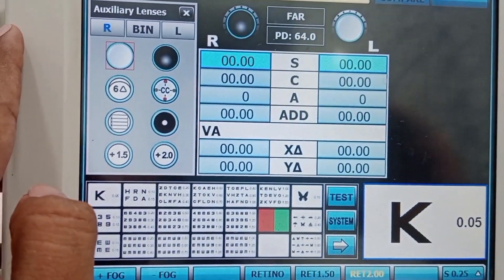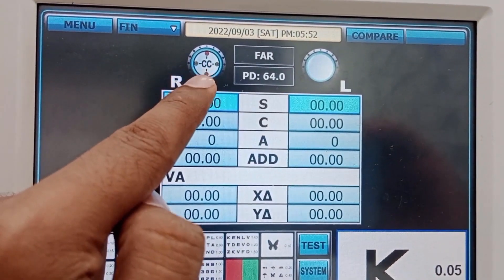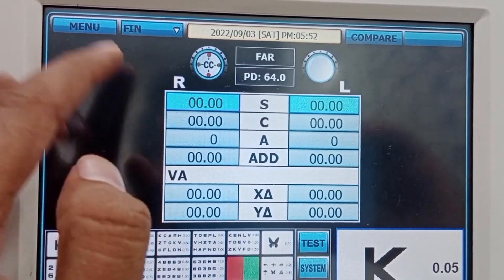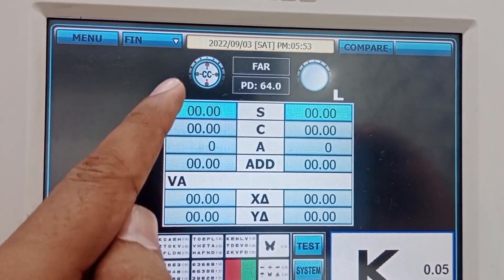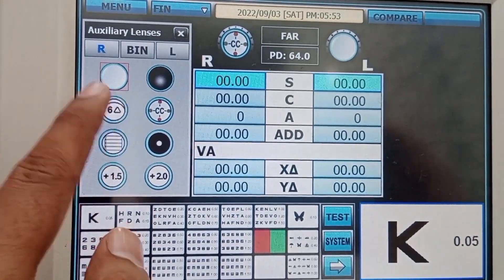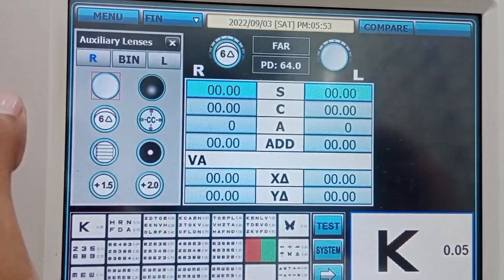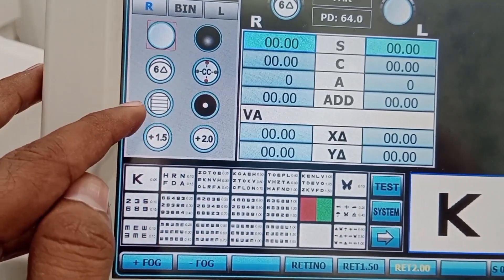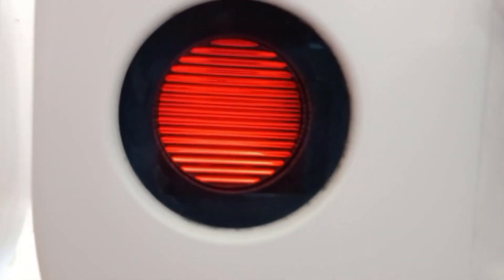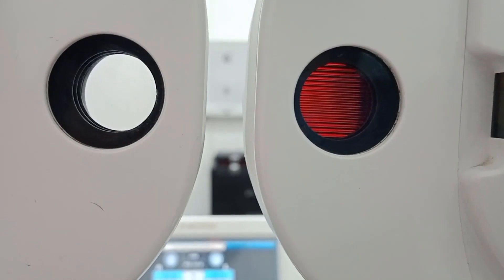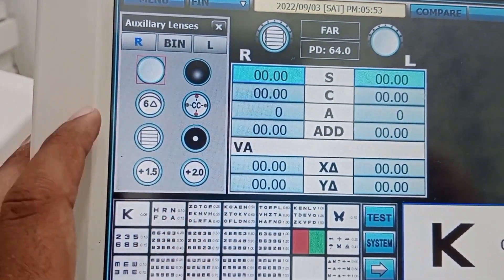The next setting is CC — this is the cross cylinder. You can perform the cross cylinder here to find the axis and power of the cylinder. The next is six prism diopters, which you can set here. The next is cylindrical striations — the Maddox rod — shown here in red color. We will learn about the Maddox rod in the next videos.